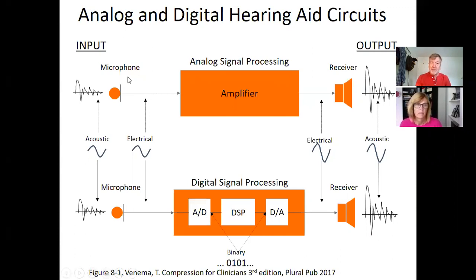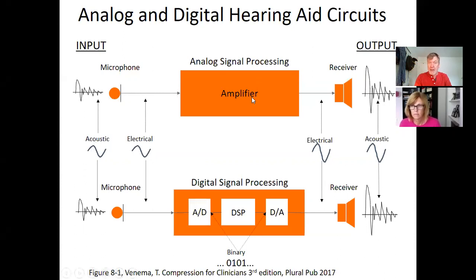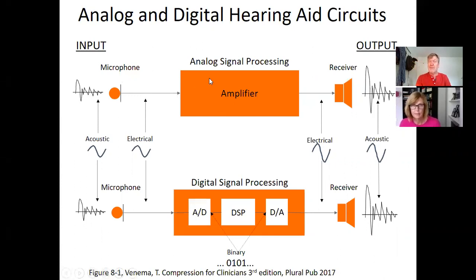Here's your input, your mic. A mic is just a transducer — it changes energy from one form to another. The mic changes sound waves into electricity, acoustic into electrical. Then that electricity was amplified by the battery-supplied amplifier, increasing the electrical current. Then the receiver, which is a backward mic — a speaker — changes electricity into acoustic energy again. So you had sound changed into electricity, and electricity changed back into sound. Analog hearing aids are all hardware: mic, amp, and receiver.